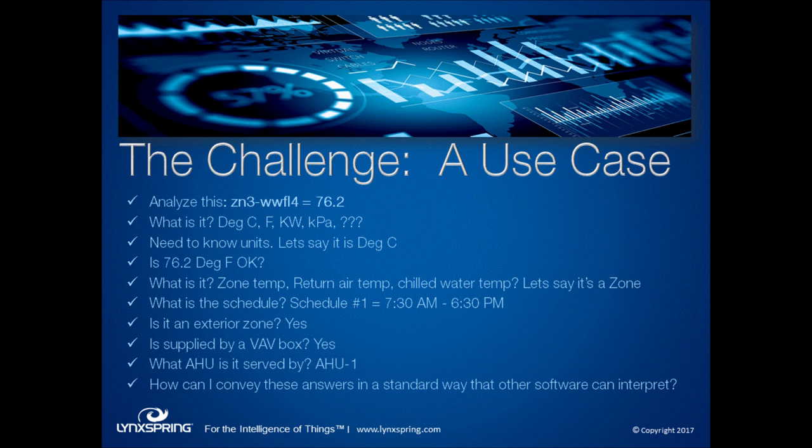Before I can analyze that, before I can say it's okay, I need to know what it is. First, I need to know units — is it degrees C or degrees F? What if it's KW, kilopascals, RPM? Historically we've used units, so it might say degrees Fahrenheit. Is 76.2 degrees Fahrenheit okay? I couldn't answer that if I don't know more. Is it a zone temperature? That's fairly warm — might be a little uncomfortable. But if it's return air temperature, 76.2 degrees Fahrenheit might be exactly where I want it. If it's chill water temperature on a hot summer day, that wouldn't be a good value.